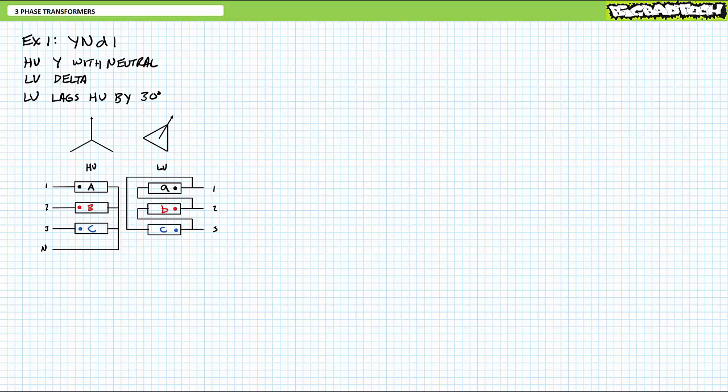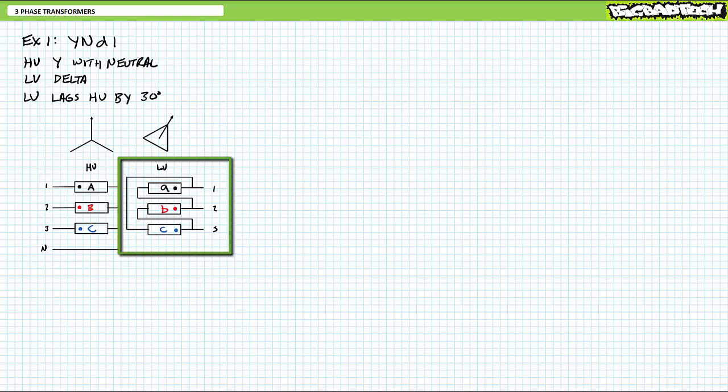It is a worthy exercise to consider how phase shift occurs between one side of a transformer and the other. The simplified connection diagram for the Y-configured high-voltage side looks exactly like you'd expect, where the non-dotted ends of the three high-voltage windings are tied together to form the central neutral connected node of a Y. The simplified connection diagram for the delta-configured low-voltage side necessitates some explanation. Whereas the Y connections tie together the similar ends — all dots or all no-dots — delta connections tie together the dissimilar ends in a continuous ring, and then the line-to-line voltages appear at the connection points.